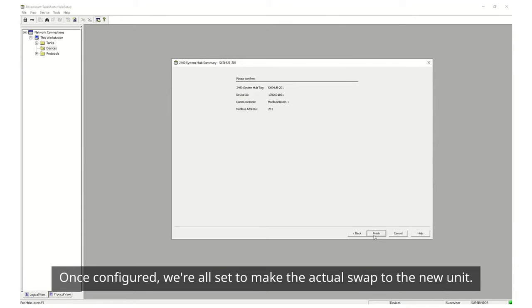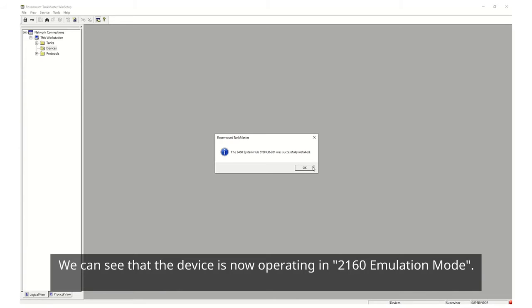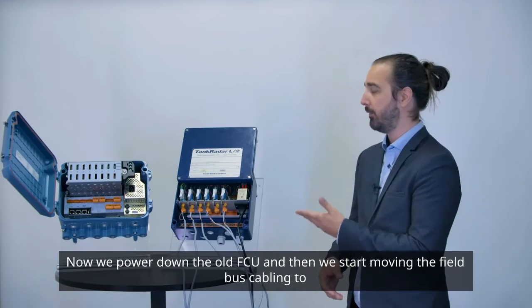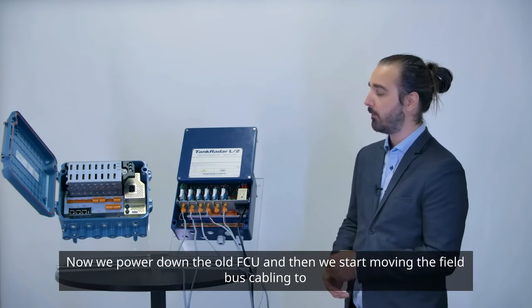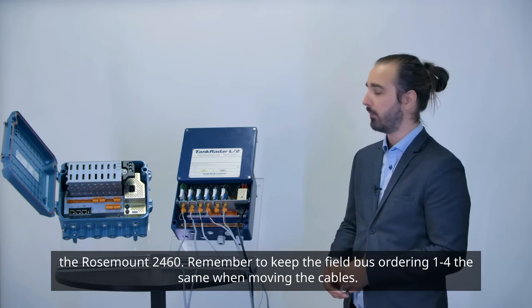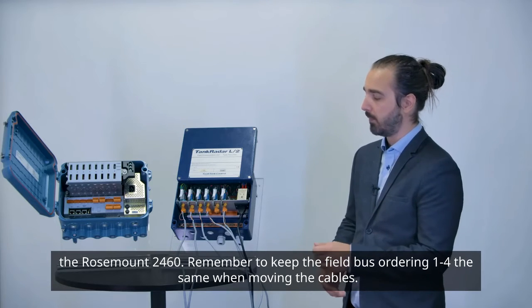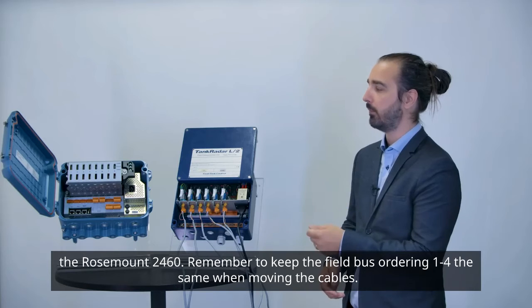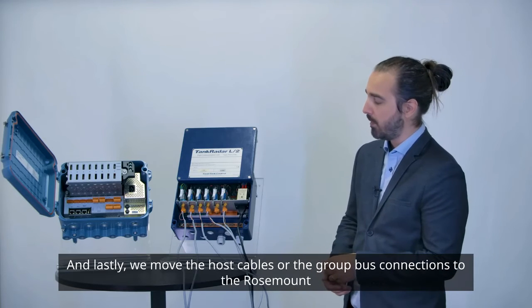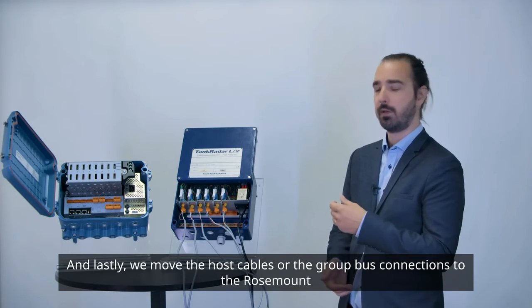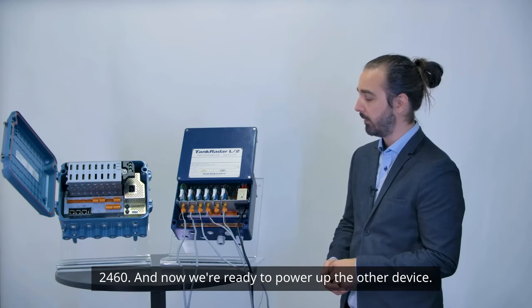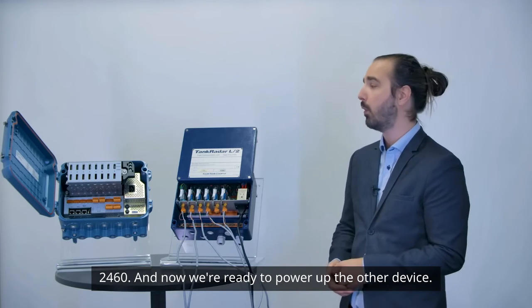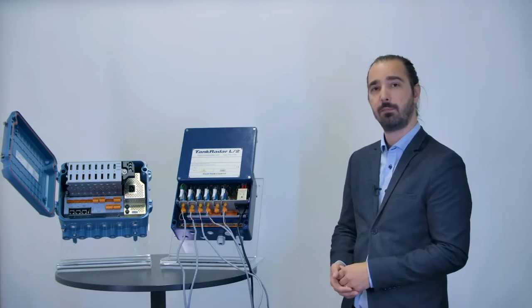Once configured we're all set to make the actual swap to the new unit. We can see that the device is now operating in 2160 emulation mode. Now we power down the old FCU and then we start moving the field bus cabling to the Rosemount 2460. Remember to keep the field bus ordering one through four the same when moving the cables. And lastly we move the host cables or the group bus connections to the Rosemount 2460 and now we're ready to power up the other device.